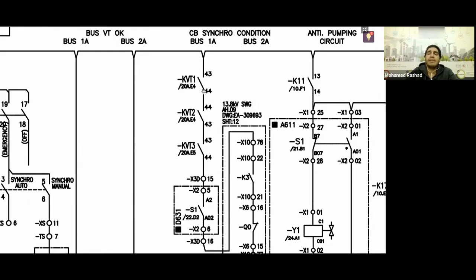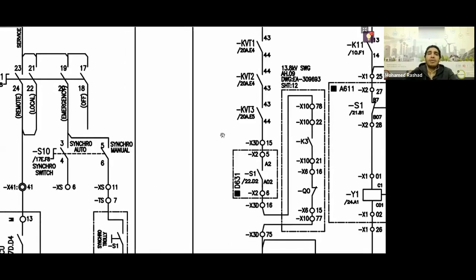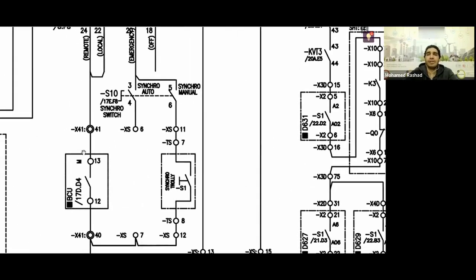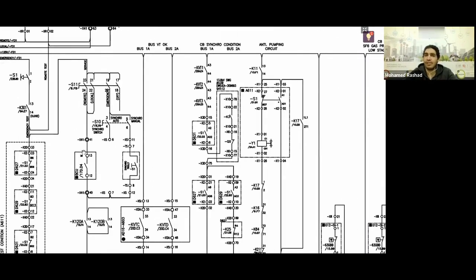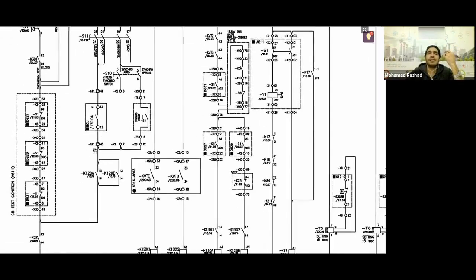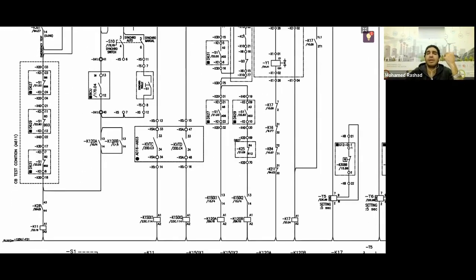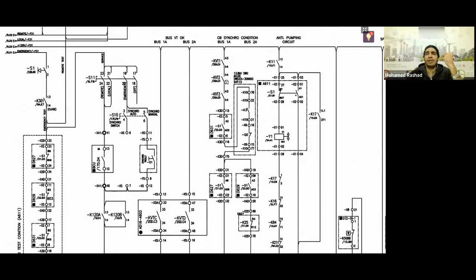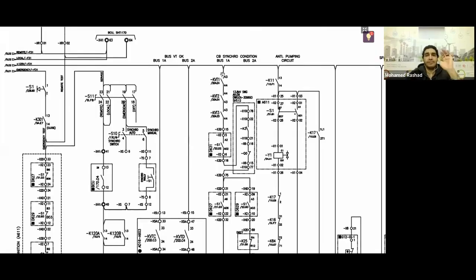You know, if one of these is different or not closed, then your circuit is open. So even if the relay detected incorrect synchronization or a synchronization error, depending on the input it receives, it zeroes out based on the assumption that the input is indeed 0. However, this could be because, for example, the VT MCB is open. So even if this is verified, you still have these 2 auxiliary contacts that won't close. Why? Because their auxiliary relay won't operate due to their circuit being incomplete. Great. So these are related to the VT.